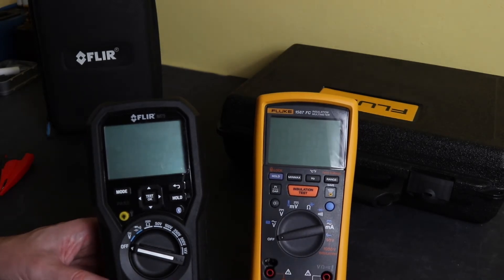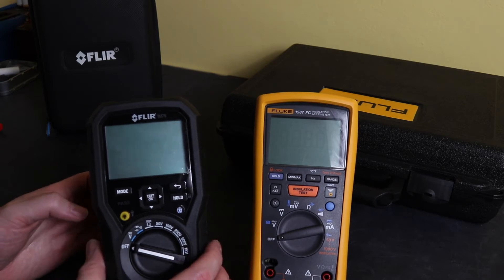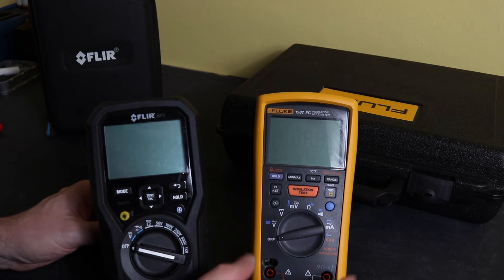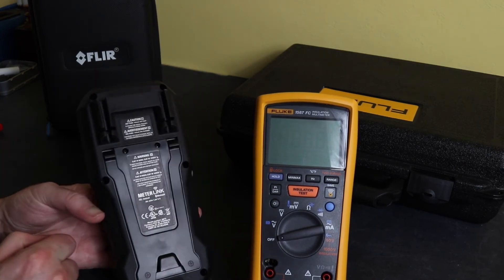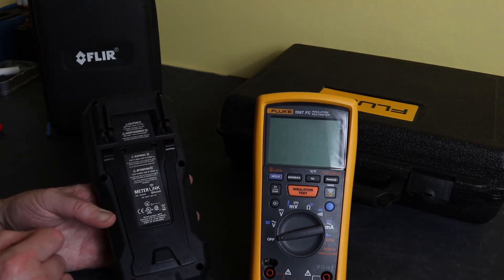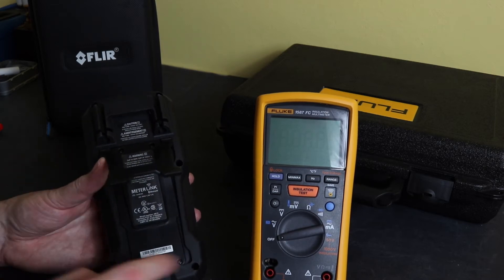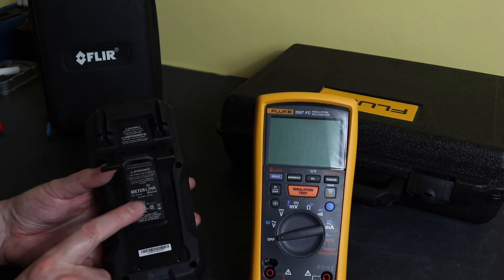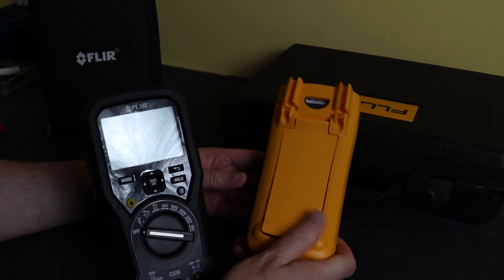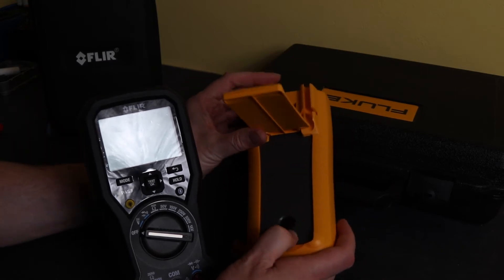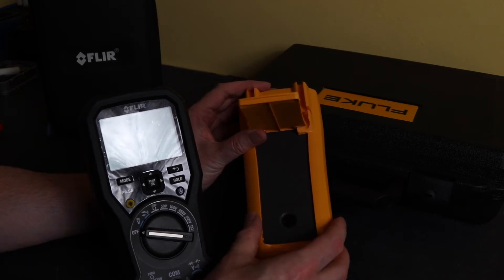So there's the two instruments sat there. Construction-wise, you have with the Flir a completely solid meter. The rubber is molded onto the plastic case. With the Fluke you've got the rubber boot that is removable. On the back of the instrument, space for hanging strap there and also to fit the probes in as a probe holder, either for the instrument in use or for storage. Tilt bail, and four screws to get into the battery compartment, which is a triple A battery pack, times six for this instrument. In comparison, the Fluke here, you also get the probe holders for storage or for whilst they're in use.